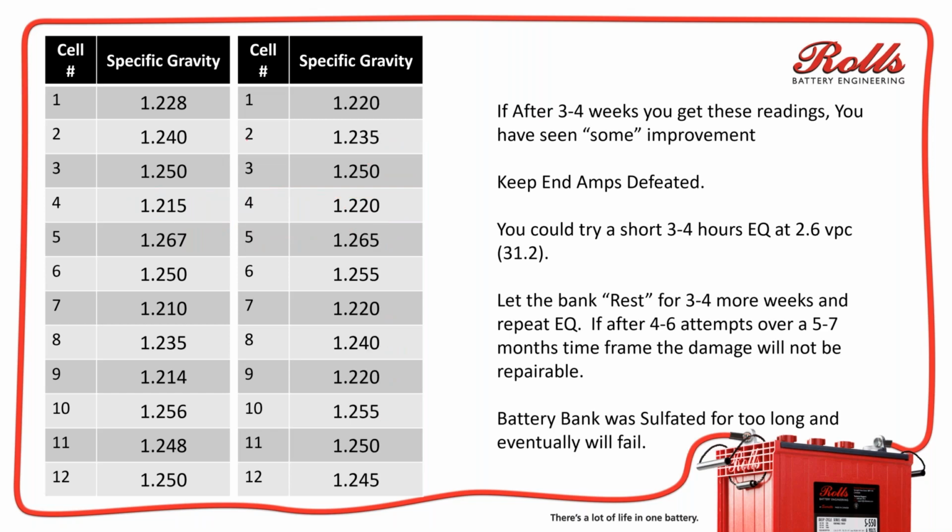If you ended up with something like this, where you see a little bit of improvement in some cells, but you don't see improvement across the rest, then there's a good chance that this battery bank was sitting too long and probably will eventually fail. It's probably not recoverable. So you want to be careful with that.